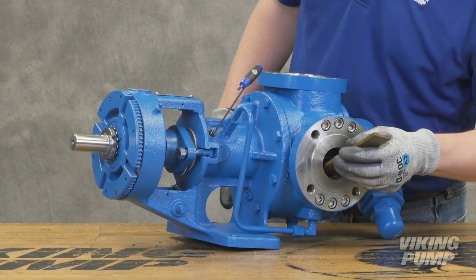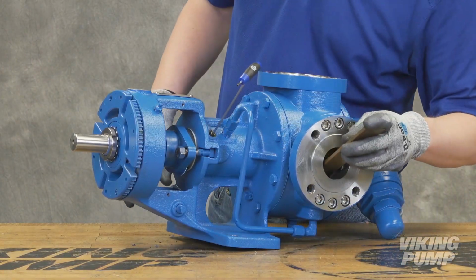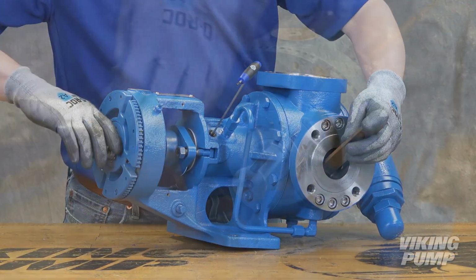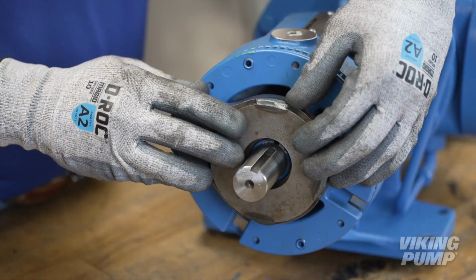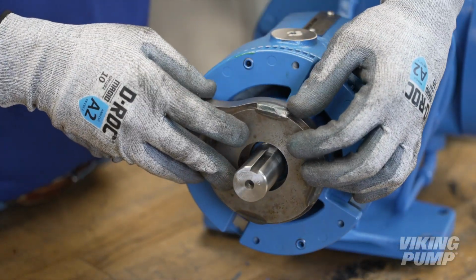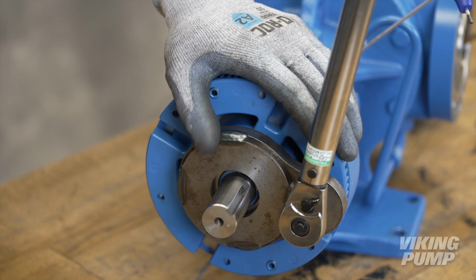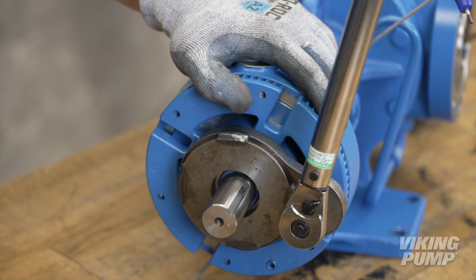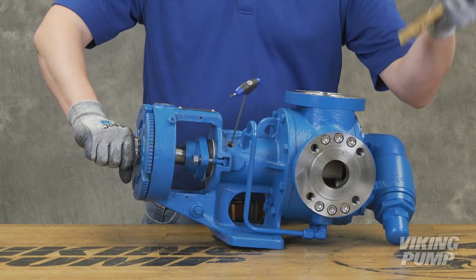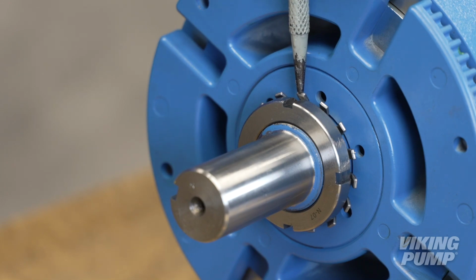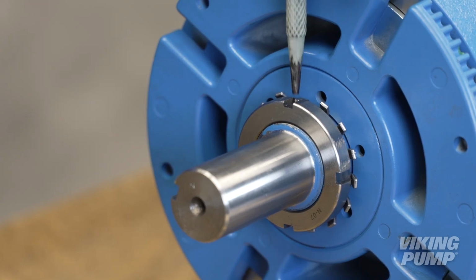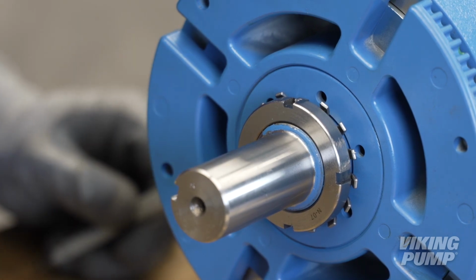Place a brass or hardwood bar into the port opening to keep the pump from turning. Torque the lock nut to the appropriate torque setting. This setting can be found in the technical service manual. Remove the brass bar. Bend a tang of the lock washer into a slot of the lock nut. If no tang aligns, continue to tighten the lock nut until one does. Failure to tighten the lock nut or engage the lock washer tab could result in early bearing failure and cause damage to the rest of the pump.